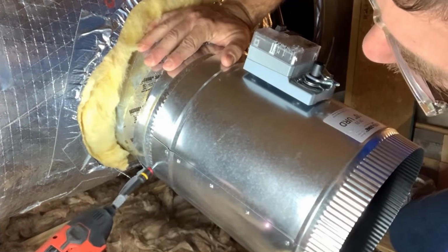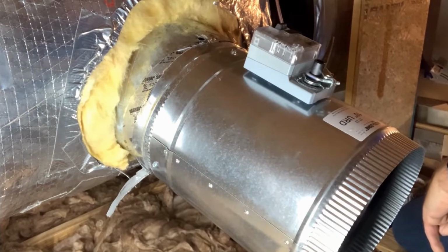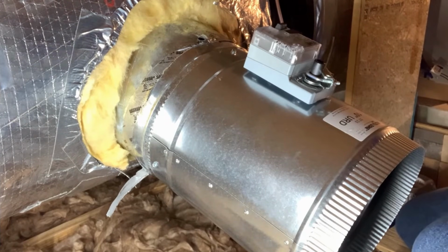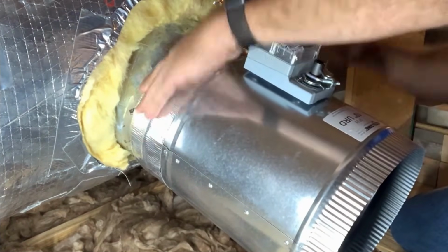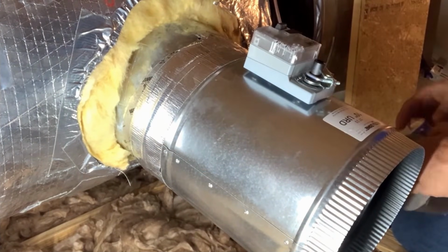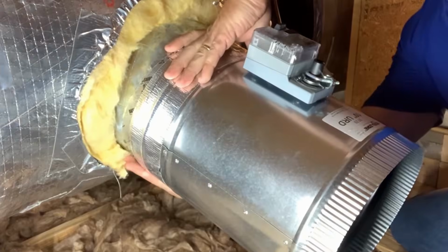Zone control system. A zone control system allows a central air conditioner to send cooled air only to the parts that need cooling. Zone control systems use dampers, individual thermostats, and variable speed blower fan motors to manage air distribution. If a house is divided into 2 zones, the upper floor and the lower floor, it's much easier to create balanced temperatures, such as cooling the upstairs only to combat rising heat, then switching for a short time to cool the downstairs.